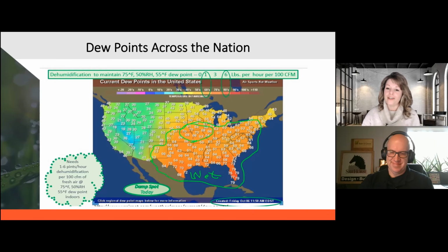So if you go on there and search for Teddy Bear, you will see all kinds of questions and topics that he's addressed and answered. But what I find most interesting is he's the first to tell you when a dehumidifier isn't going to fix it. There's a lot more to think about than just adding a dehumidifier and thinking it's going to control the moisture issues. We really need to make sure that we've minimized the air infiltration as much as possible. We need to make sure that the ductwork is sealed, and that everything else is working as close to correctly as we can get it. And then we apply a dehumidifier.